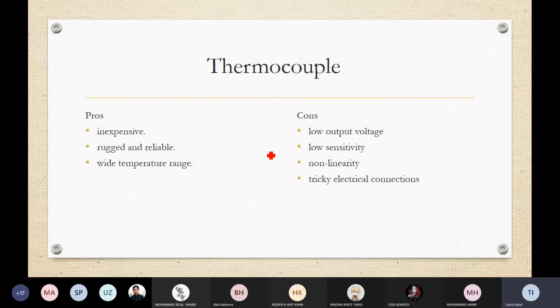So the benefit of this thermocouple is that it is inexpensive as compared to thermistor and RTD. It is reliable, it has a wide range, but the problem is its output voltage is very low, and therefore we need signal conditioning. Then it is less sensitive. If there is a smaller voltage change, 20 microvolts per degree change, then the thermocouple cannot detect that.